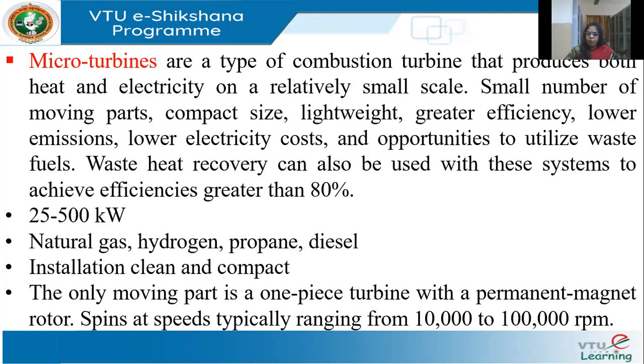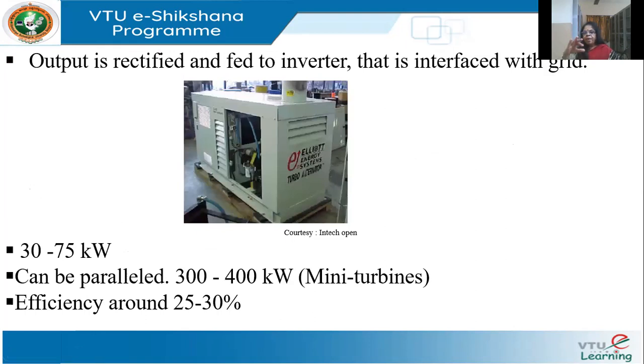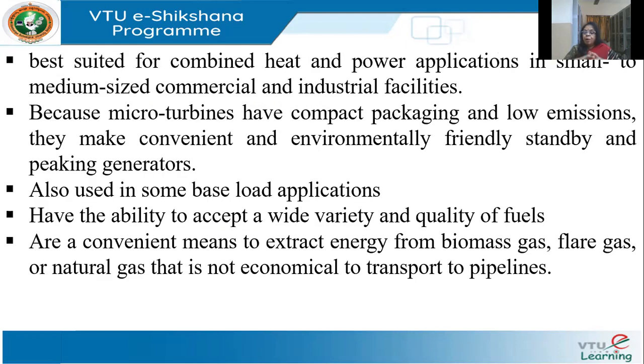The fuel used in micro turbines is natural gas, hydrogen, propane, or diesel. These installations are clean and compact — just one small turbine with a permanent magnet rotor, with a typical rotational range from around 10,000 to 100,000 RPM. The output is rectified, then inverted, and interfaced with the grid if necessary, or inverted directly for loads. You can parallel them and increase power capacity up to around 400 kilowatts — these are called mini turbines. The turbine alone has about 30% efficiency, but including heat recovery it can reach 80%.